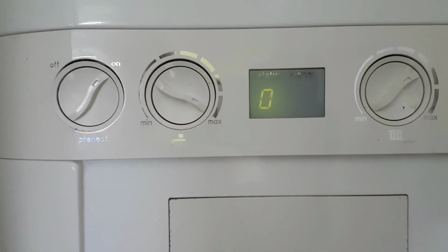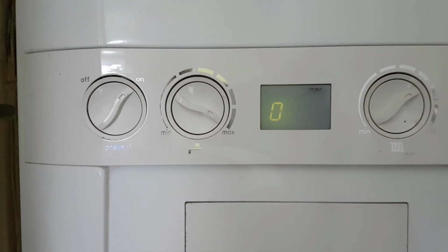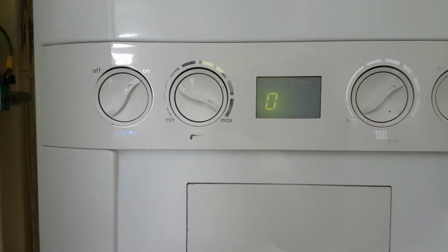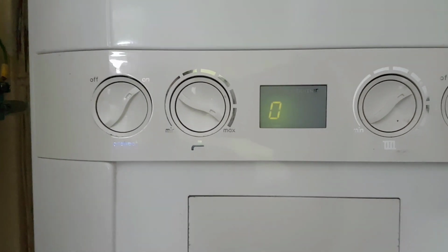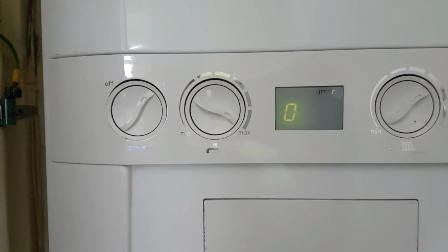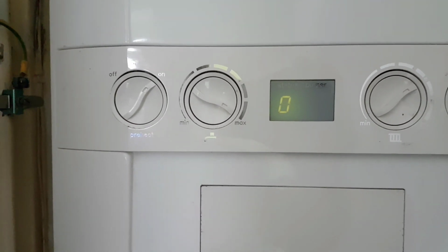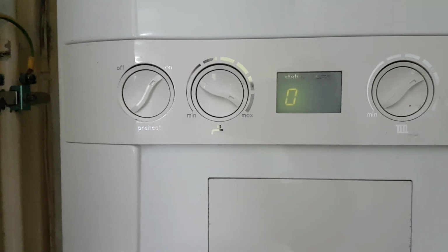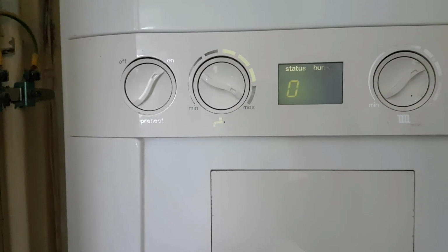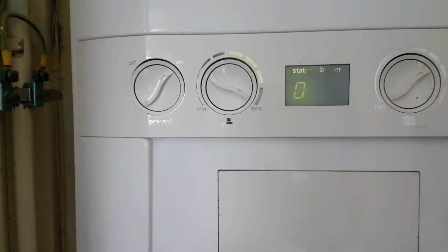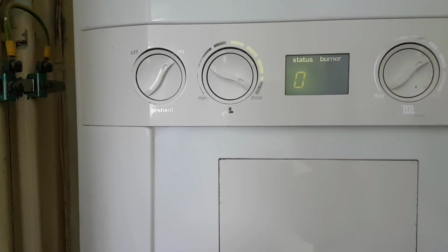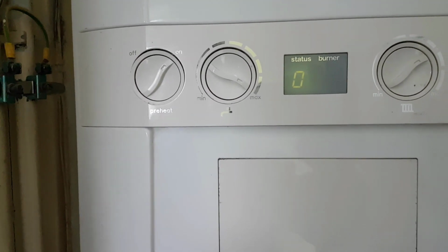You can see the status, it's now on 0. You can hear the shower in the background running. So this is conclusive proof that the flow turbine is not detecting the flow of water. So this is how you diagnose the flow turbine. It's not sometimes straight obvious, so you have to observe it just like what we've done. Maybe take 3, 5, could take 6 or 7 minutes.